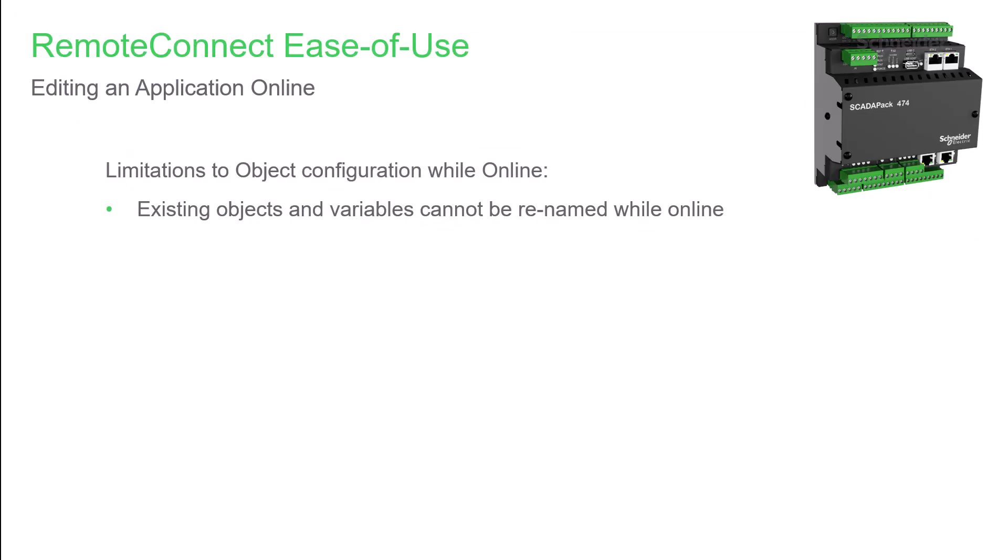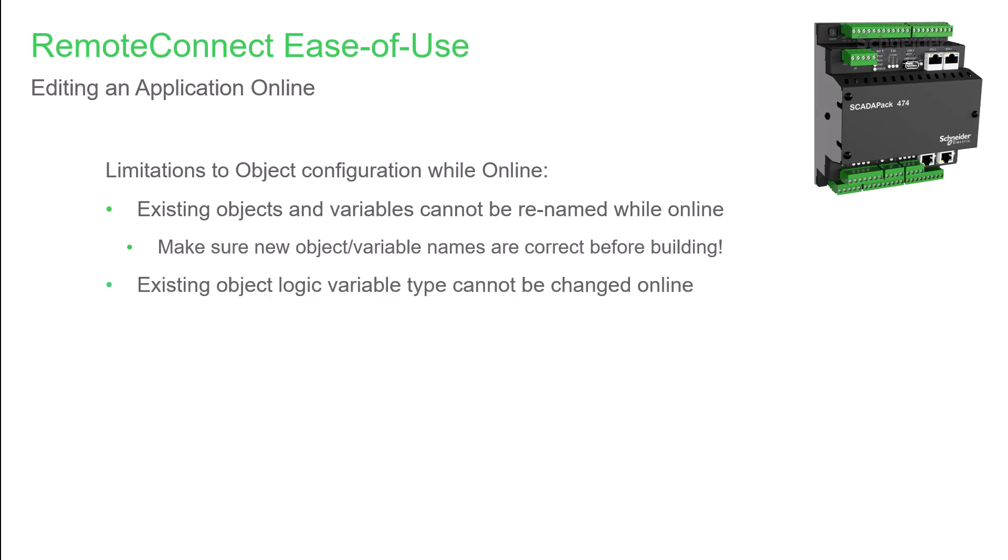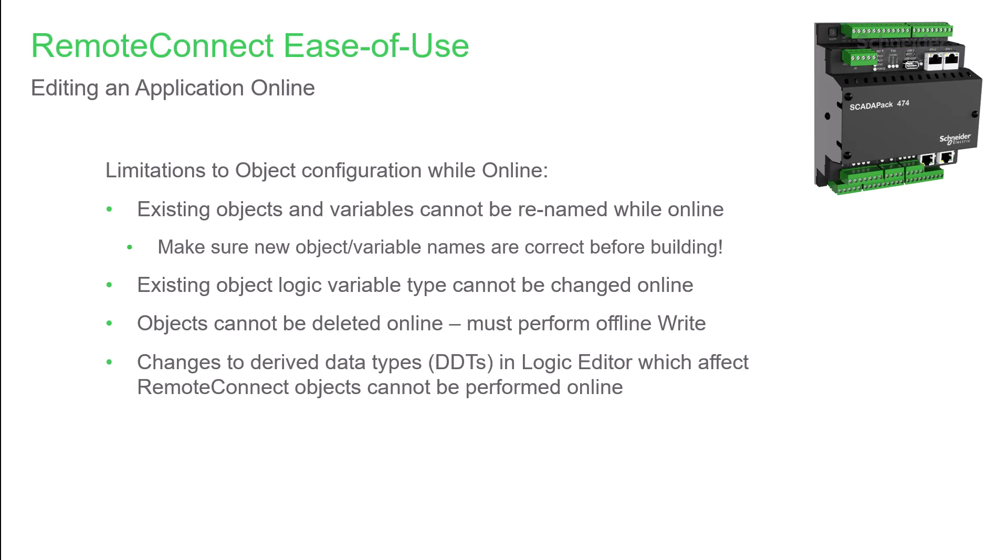And there are limitations to be aware of when editing objects and variables online. First, existing objects and variables cannot be renamed while online, so it's important to verify that any new object names are correct before building. Existing object logic variable types cannot be changed while online, so again, verify these details beforehand. Objects cannot be deleted during an online editing session. You'll either need to leave them unused or do an offline write that will momentarily stop the logic execution. Also, editing of derived data types in Logic Editor that affect RemoteConnect objects cannot be done online.